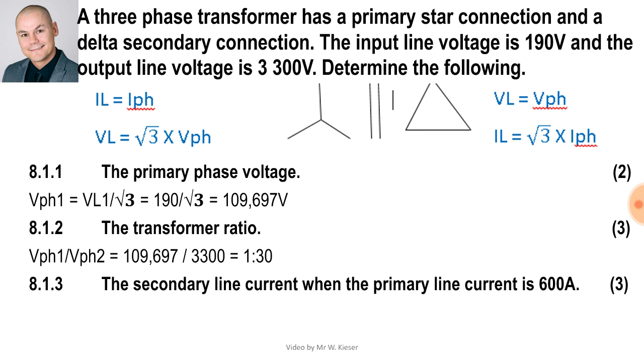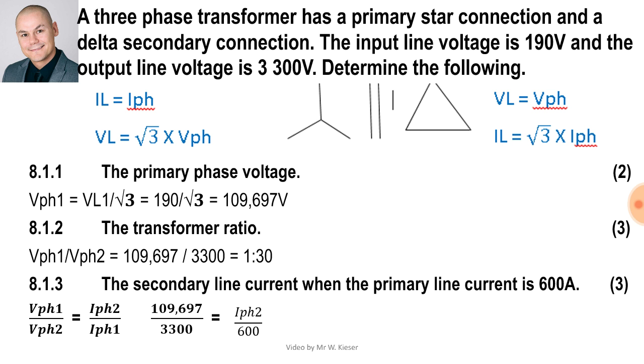To calculate the secondary line current when the primary line current is 600 amps: on the primary side it's star connected, so IL equals I phase. The line current of 600 amps is also our phase current. On the secondary side, to find the line current we first work out the phase current using the equation: V phase one over V phase two equals I phase two over I phase one. Substituting: primary phase voltage is 109.697, secondary phase voltage is 3300, secondary phase current is the unknown, and primary phase current is 600 amps.